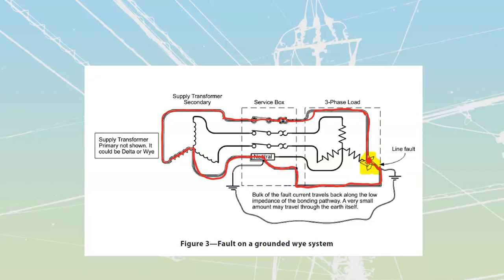It is always, always, always going to have a complete path. We never have current that just hits a fault and just kind of disappears into the earth. Woo, where does it go? It doesn't do that. It's always trying to find its way back to the transformer. Even if we do have a little bit that is going to make contact with the earth itself, it is still going to use that earth to carry itself back up to the neutral, where it is going to rejoin with the rest of the current and go back to the supply transformer.